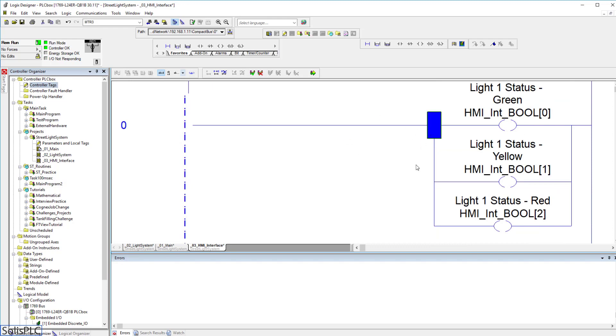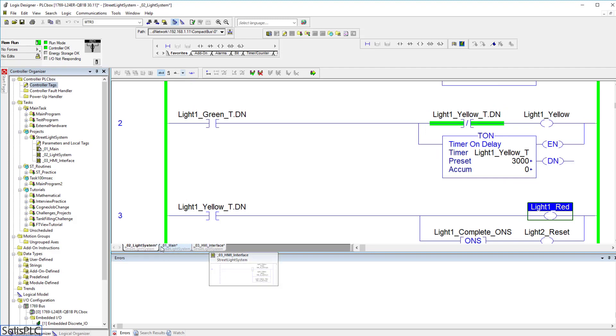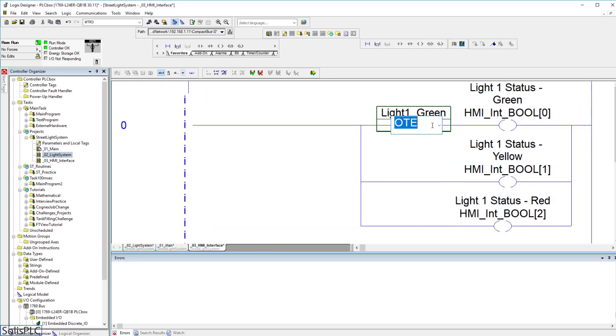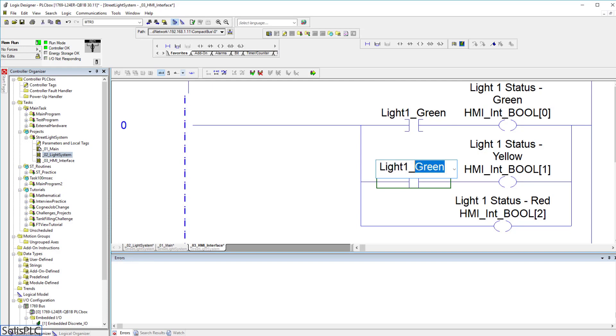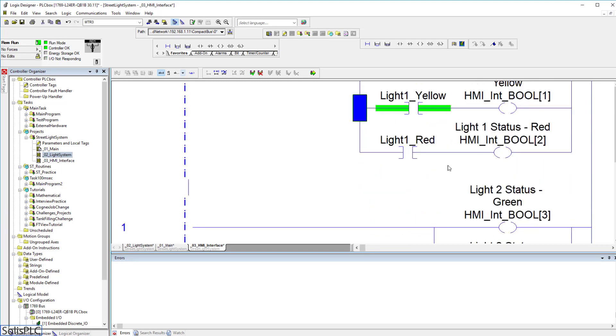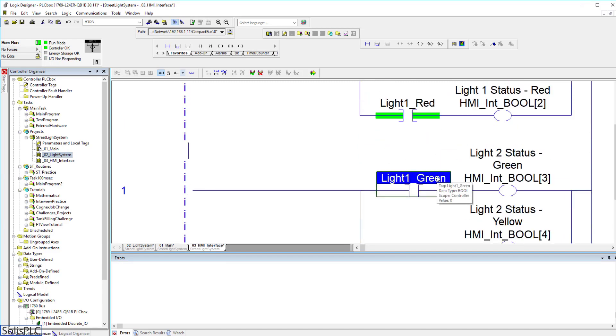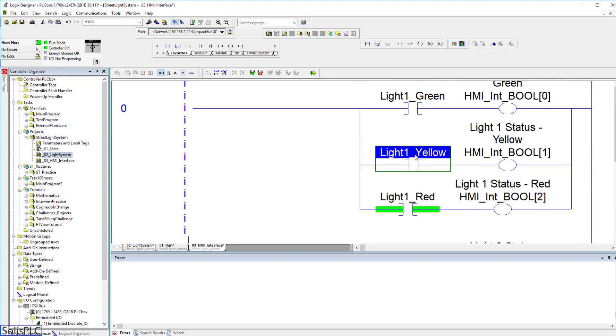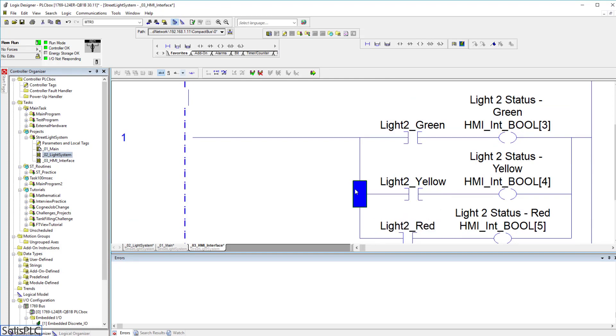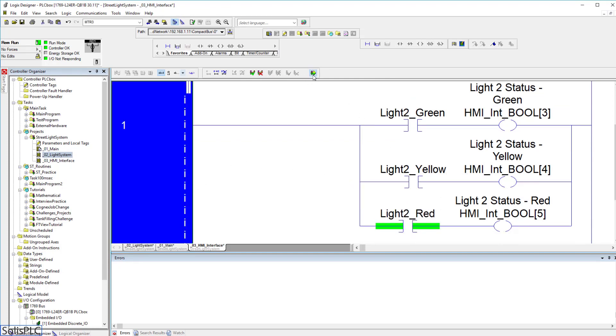Of course we need to energize those bits — right now they're just blank booleans, but we need conditions to energize them. I'm going to go back into the light system by clicking on one of the tabs at the bottom, and I'll use the tags we've already used to program our system. I'll Ctrl+C those tags, go back to the HMI interface, and paste them in. The reason it's important to create a separate HMI interface is that these green, yellow, and red tags can be used for many functionalities, but the HMI interface should have a single endpoint, making it easy for a programmer or HMI developer to interface with the system. So light2 green, light2 yellow, and light2 red — and of course we need to change this one to a two. We'll develop the HMI fully in the next lecture.